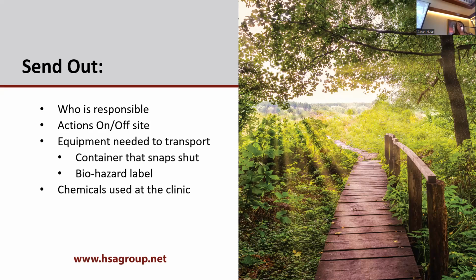And then what chemicals are being used at the clinic for that pre-soak or the cleansing? Make sure you're appropriately storing that at your facility, because it's usually a very high level chemical and it's a safety concern for patients. I have seen it quite often in the procedure room, stored in a cabinet, and then there's the tub on the counter, and patients are coming in for procedures while they're sitting there soaking. That would not be considered secured. The chemical's not secure. The instruments that could be considered sharps, the biohazardous materials in that element, they're not secured from that patient safety perspective. So really think through what responsibilities we have at the clinic. What is our process? And are we considering all aspects of patient safety regarding where we're storing these chemicals and processes?